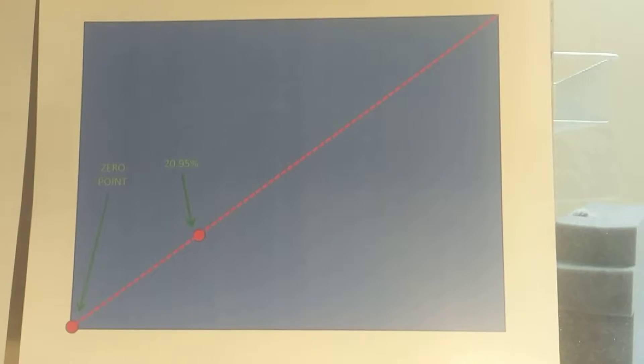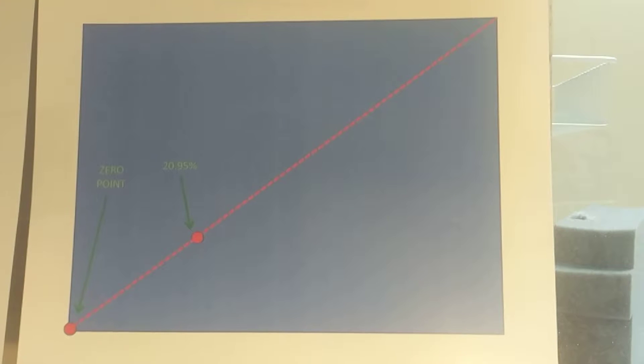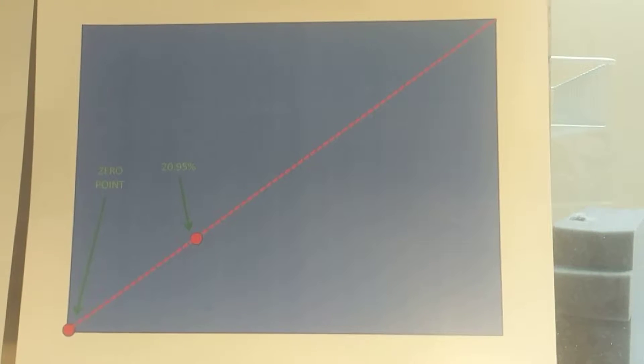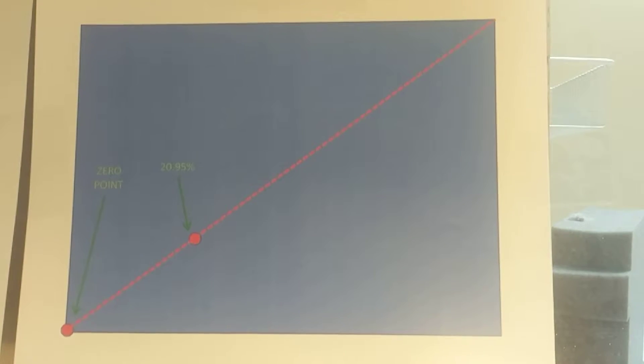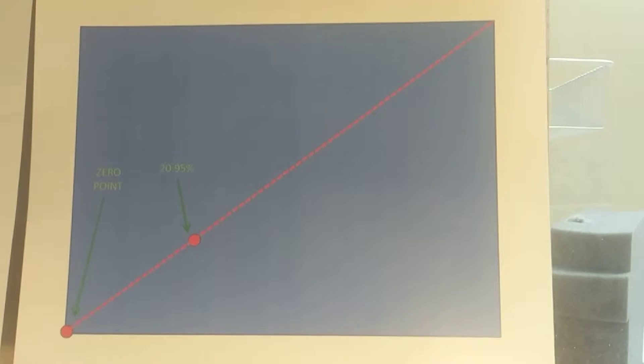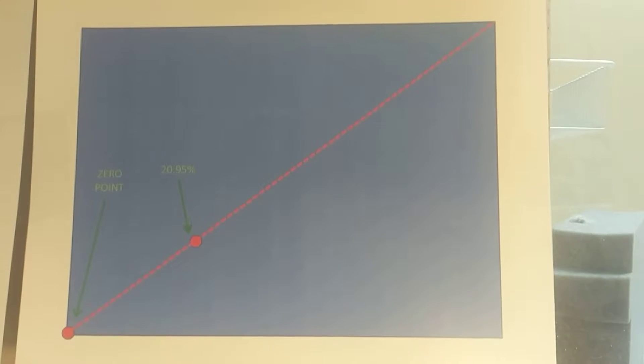Now if you were to change elevation, you'll see a different reading on the instrument. That's not because there's a different concentration of oxygen, it's simply that there are fewer oxygen molecules overall at different elevations, and we're going to go through how to adjust the instrument for that and some basic validation steps.